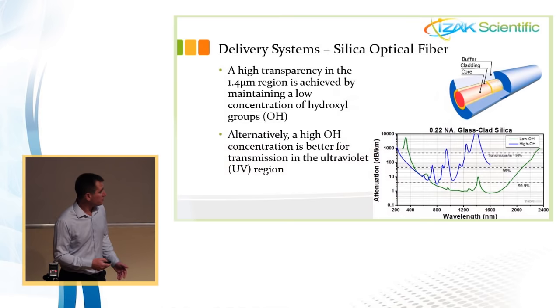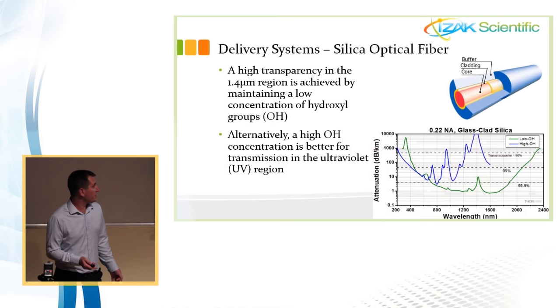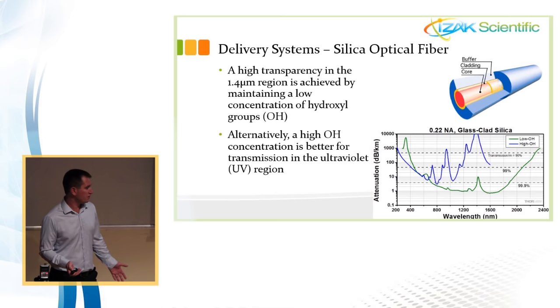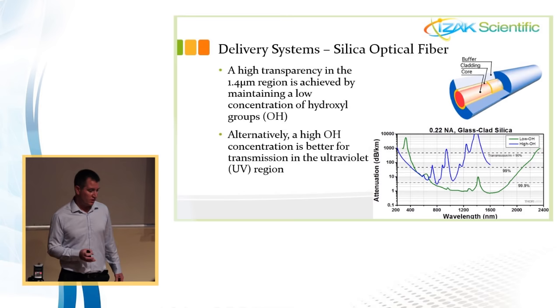After we choose the laser, the fluence, the power, and the pulse width, now we want to deliver it. How can we deliver the light or the energy inside the body? If we are speaking about the near IR region, up to 2.1 or 2.2 micron, there is an optical fiber, which can transmit the light very well, and of course the fiber is inserted into an endoscope or a cystoscope or another scope that fits the application.